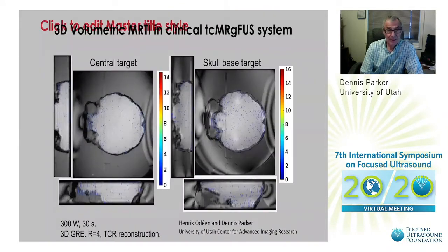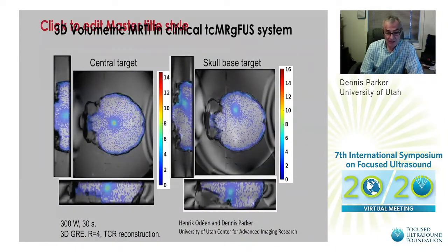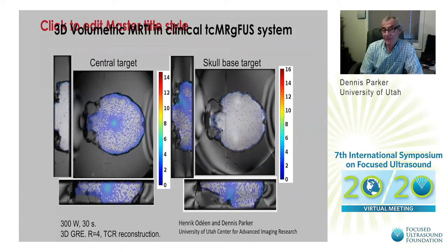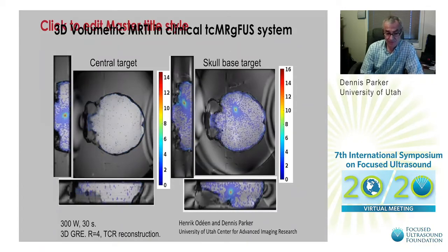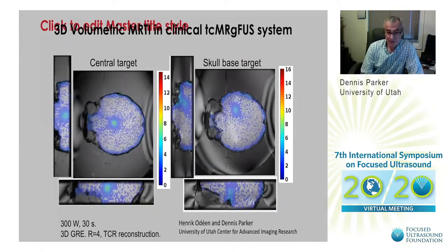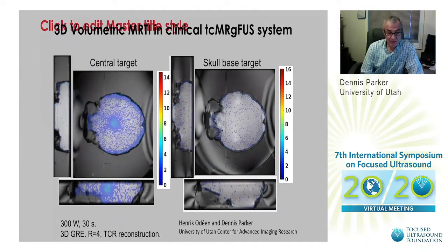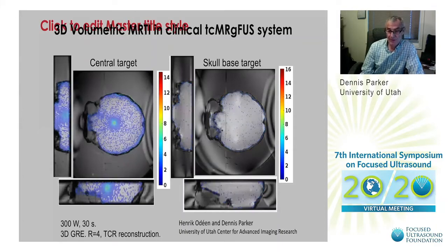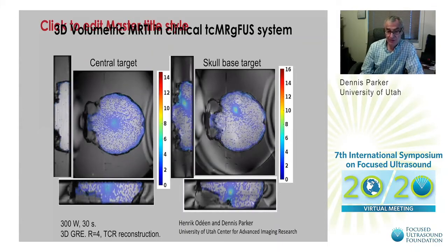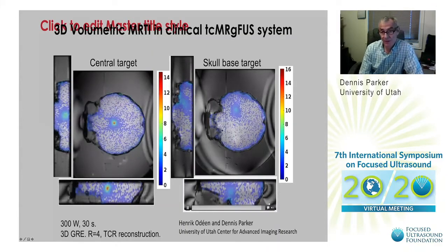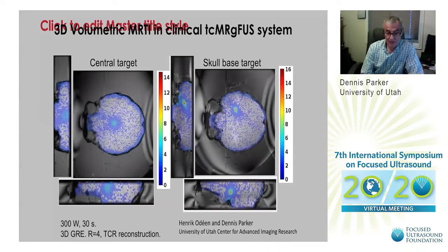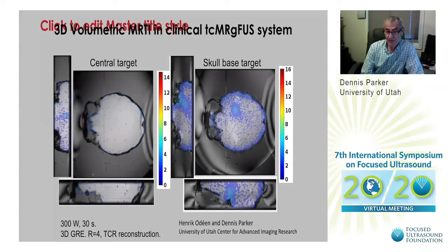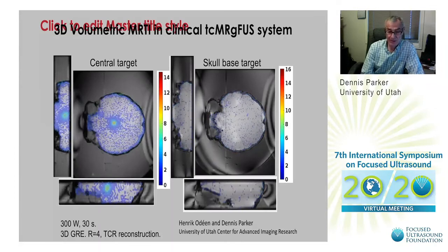This can be seen, let's see if I can get this to run, in these actual heating applied to a gelatin-filled skull using the Insightec system. Heating at the nearby bone surfaces can be equal or exceed heating at the focus and should be monitored. And we and others are working on fully 3D MR temperature imaging methods for these studies.